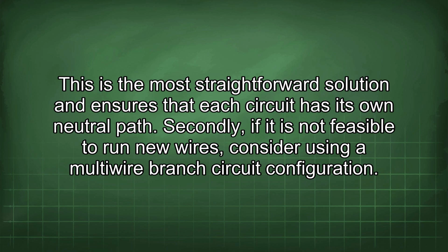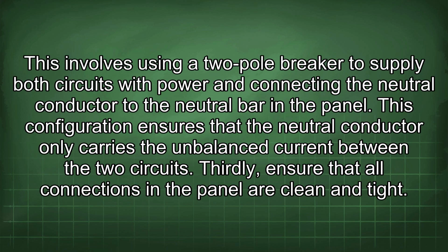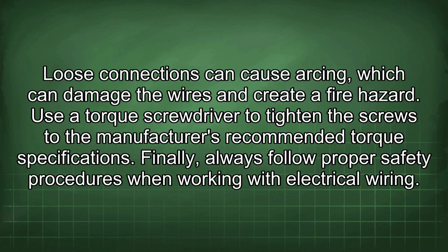Secondly, if it is not feasible to run new wires, consider using a multi-wire branch circuit configuration. This involves using a two-pole breaker to supply both circuits with power and connecting the neutral conductor to the neutral bar in the panel. This configuration ensures that the neutral conductor only carries the unbalanced current between the two circuits. Thirdly, ensure that all connections in the panel are clean and tight. Loose connections can cause arcing, which can damage the wires and create a fire hazard.